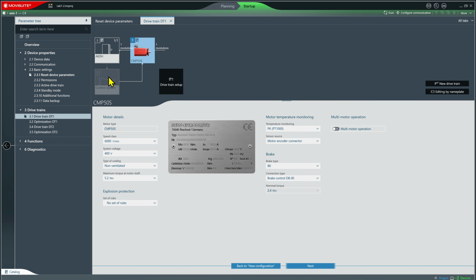Now we haven't selected everything yet, so a few things aren't complete. And we do need to go down first of all and double check that everything's right for our motor. And in fact, it's not, because the speed class is wrong. This is a 4,500 RPM motor. So I need to change that. The system voltage is fine. The ventilation's fine, the torque at the motor shaft is fine, so that's all good.